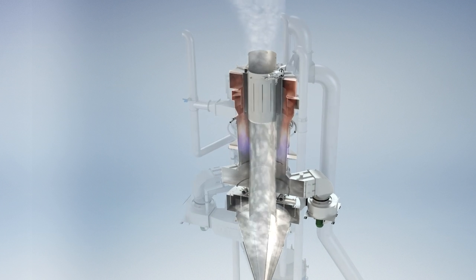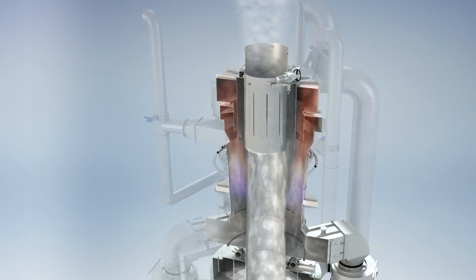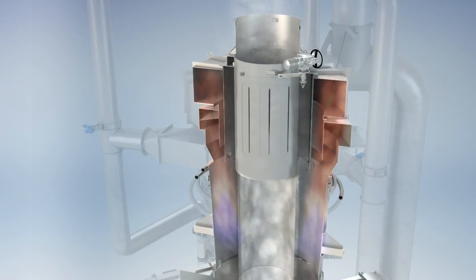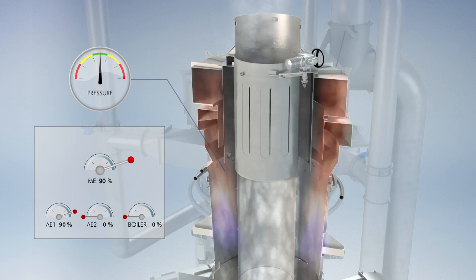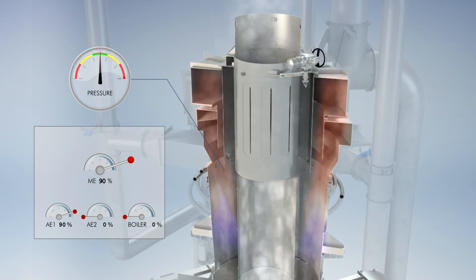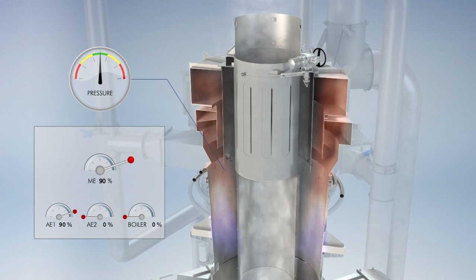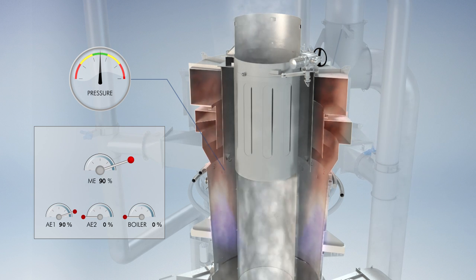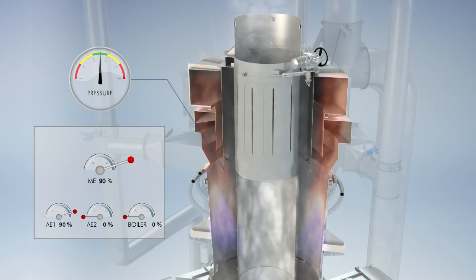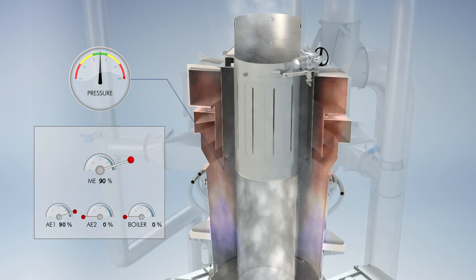The fans are configured to always have a higher capacity than the accumulated exhaust production. Combined with a gas recirculation mechanism, the pressure at the common gas meeting point is maintained at ambient level, irrespective of the amount of exhaust gas fed to the system.